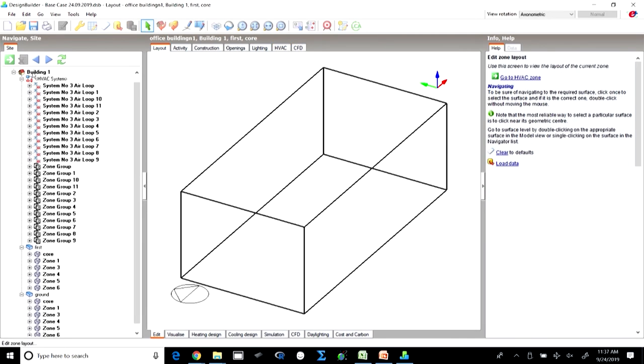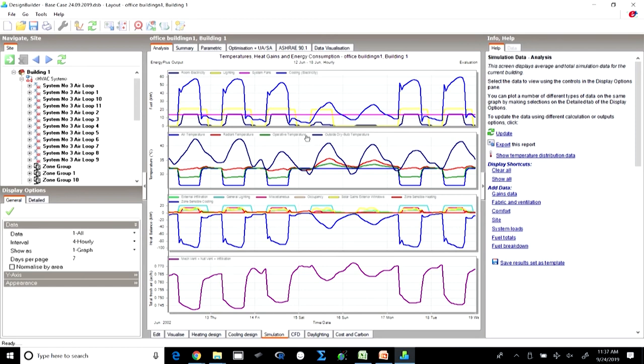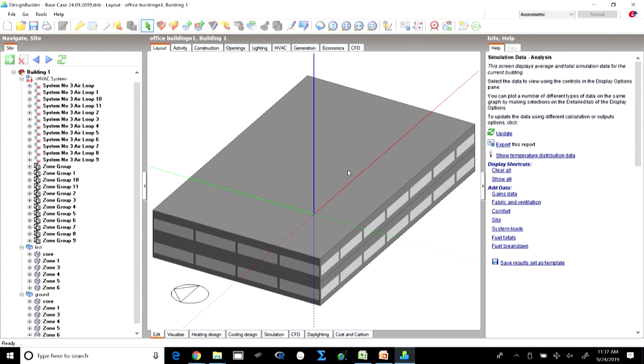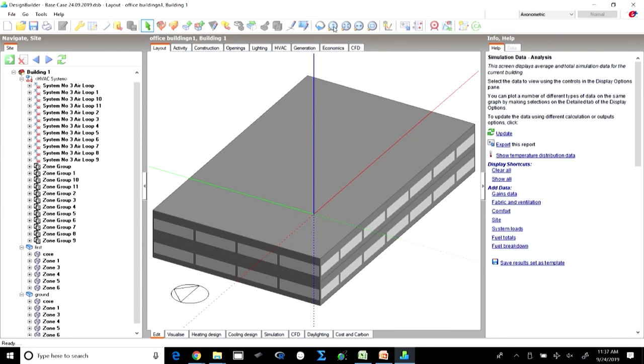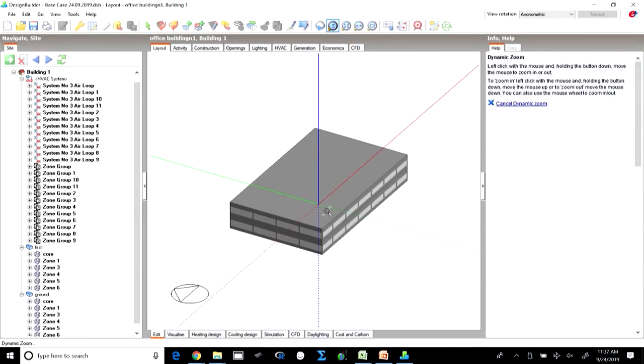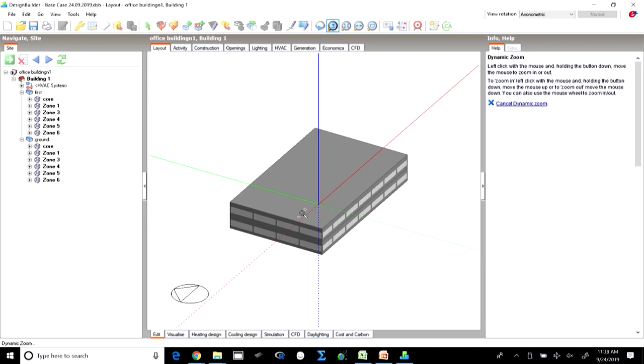The model was completed in every respect, and then we simulated the case with the building oriented towards north and achieved the results. To calculate the average performance of the base case, we rotate the building and create four different cases by rotating 90 degrees each time. We simulate each of these four cases oriented in four different directions for annual simulation — 365 days on an hourly basis, 8,760 hours. An average is then calculated as the performance of the base case, which we will use to compare whether the proposed case is performing better.